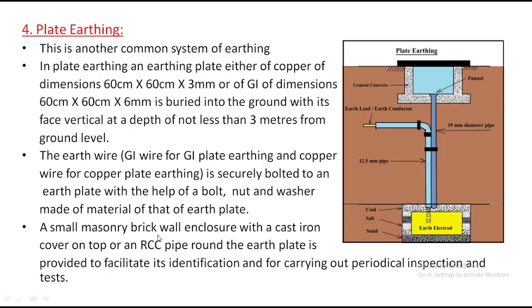A small masonry brick wall enclosure with a cast iron cover on the top. Look here, by using bricks we can make a tunnel on the top, or an RCC pipe round the earth plate is provided to facilitate its identification. It is useful for identification and for carrying out periodical inspection and tests. From this point we can test whether the earth plate is working properly or not. We can also pour water through it to maintain the conductivity.